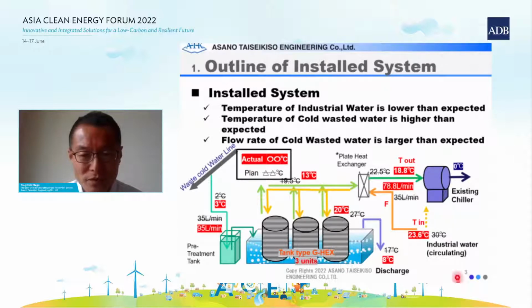For example, the black text values are from the preliminary survey, and the red text values show the data as of 17th December last year, just after the start of main operation. The temperature of the industrial water is 23.6 degrees, not 30, about 6 degrees lower than expected. The cold wasted water temperature is actually 3 degrees, 1 degree higher than expected. The flow rate of the cold wasted water is 95 liters per minute, and the industrial water is 78.8 liters per minute, almost double or triple what was expected.